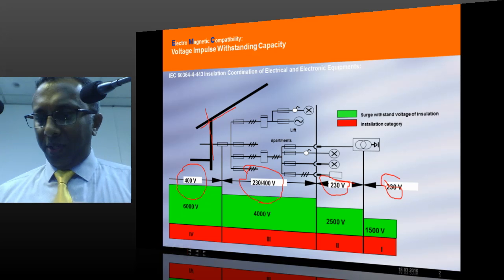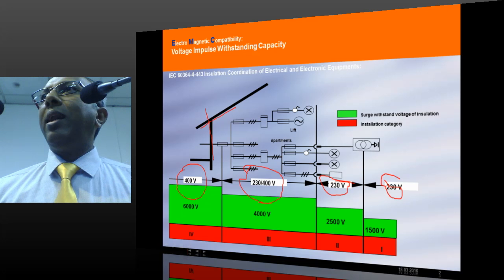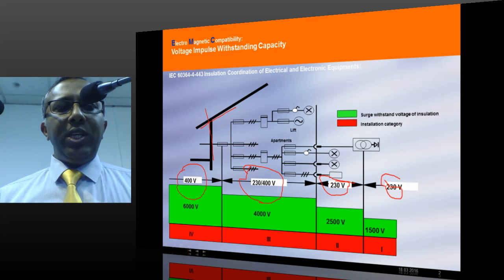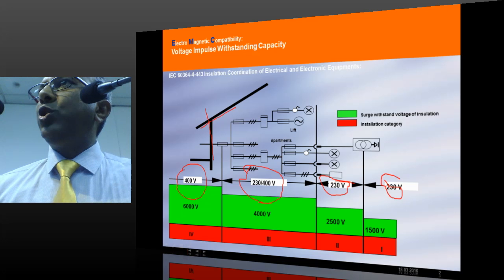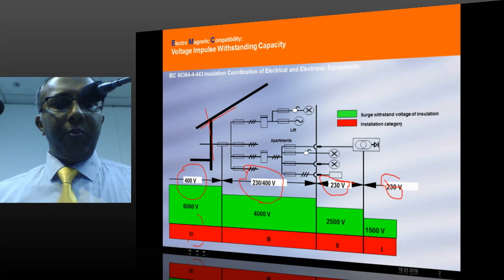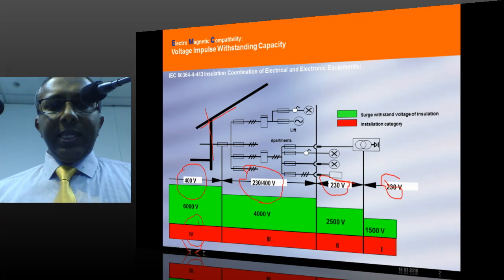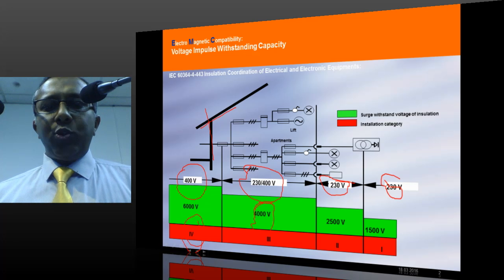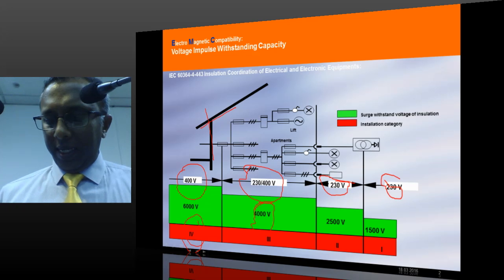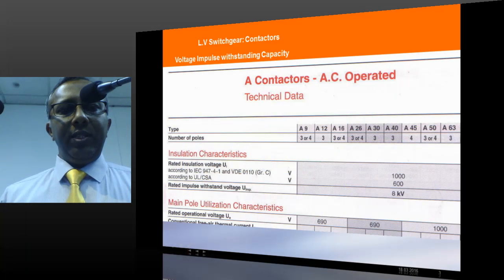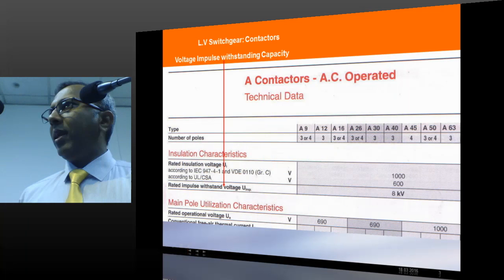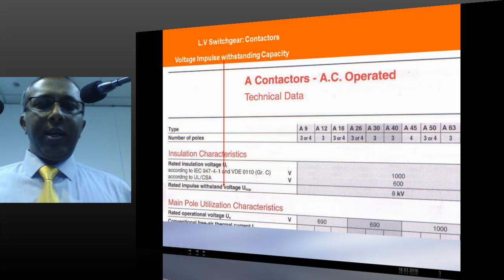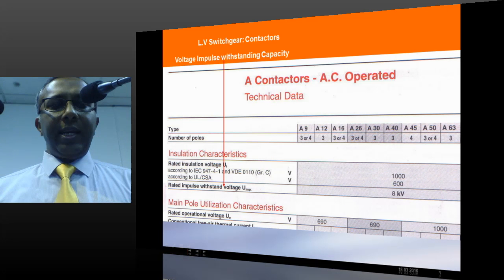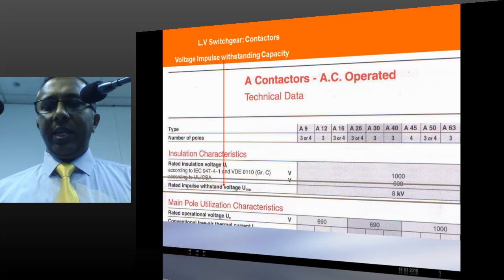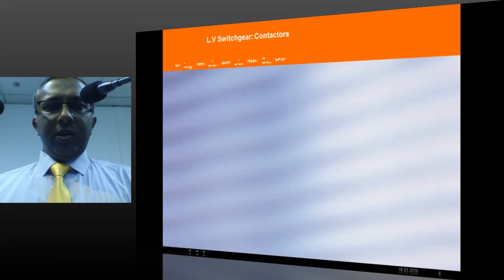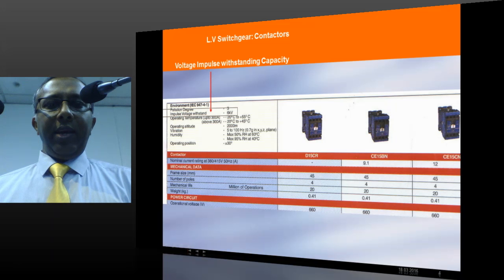I will just show you some examples. Once when you install an electrical apparatus into your building, please note that at the origin of installation we are allowed to install equipment of installation category 4. At the sub distribution board, the electrical apparatus should be installation category 3, and then installation category 1 and 2. What is this? You see, rated impulse withstanding. This is from the catalog of an ABB contactor. Now you can see rated impulse withstanding voltage. See here, this is 8 kV. Another contactor, 6 kV.